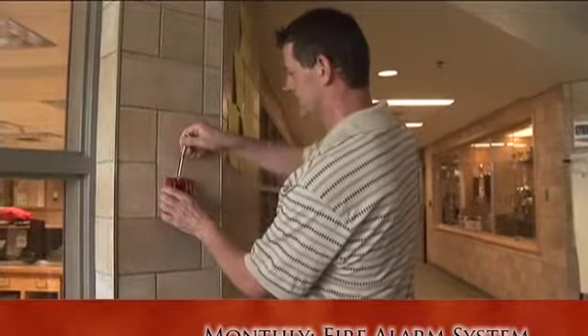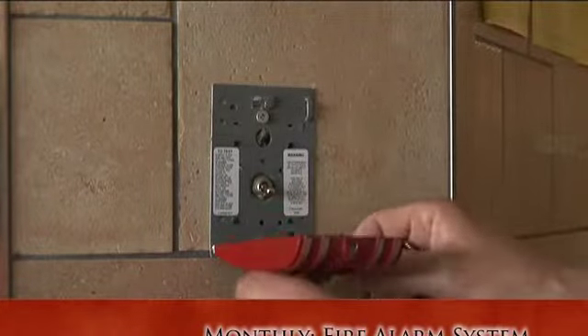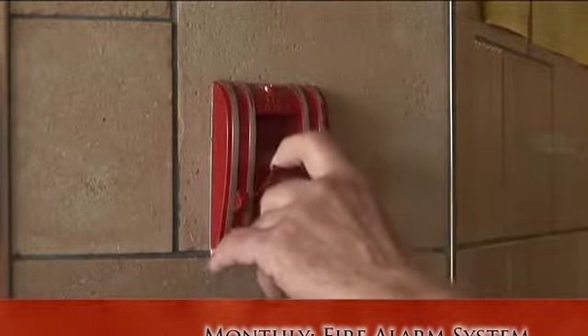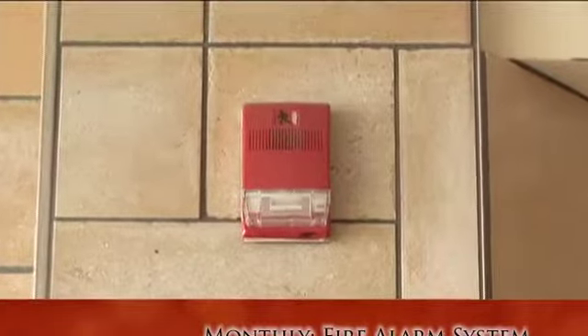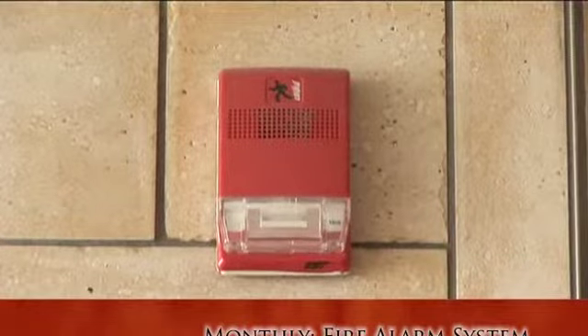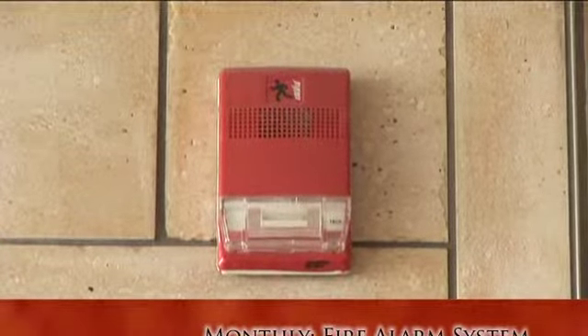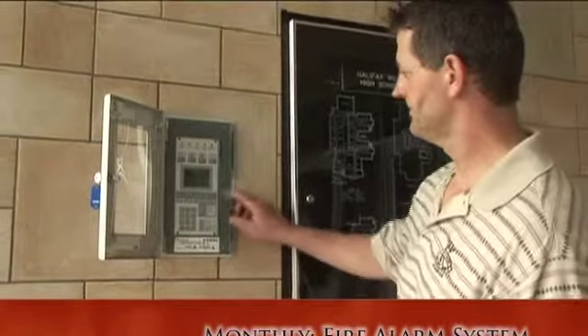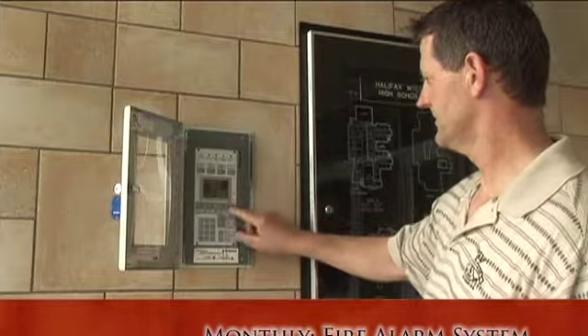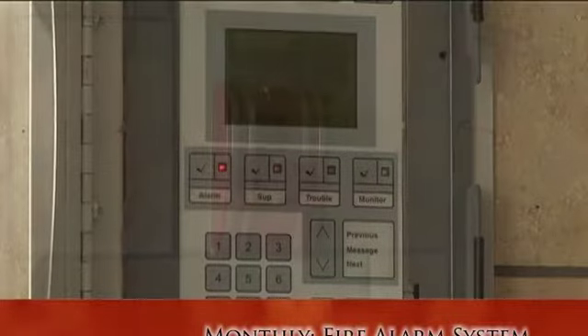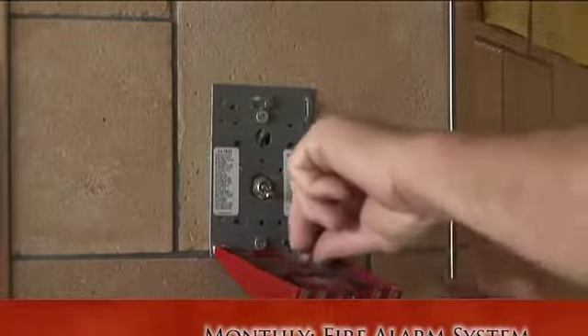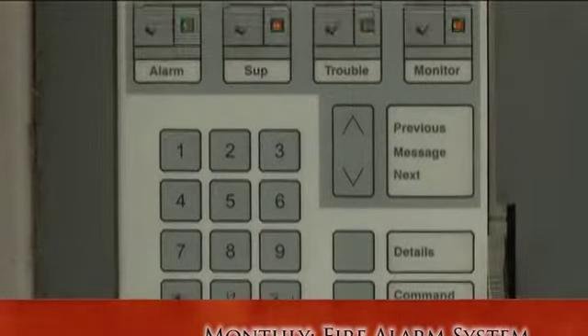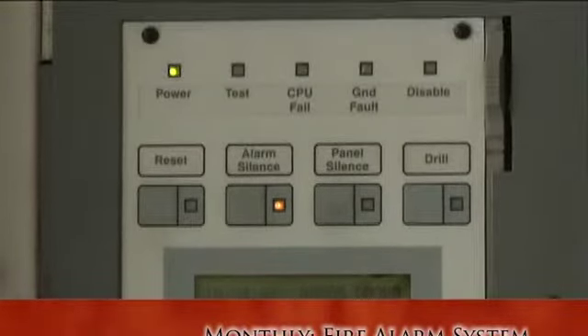On a rotational basis, one fire alarm manual pull station device in the building must be operated and trigger a fire alarm condition. Once you've done that, check all the audible and visual alarm elements in the school to ensure they're functioning correctly. Also, check the main fire alarm panel to make sure the tested devices are annunciated correctly. If any of these tests don't provide their designed function, contact your supervisor immediately. After the test, ensure that the system is reset and that only the power on indicator is illuminated. You'll then need to contact the central monitoring station to let them know the test is over.